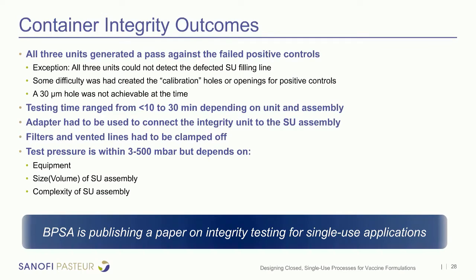So all 3 units generated a pass against the failed positive controls and the negative controls, as mentioned, with the exception of the single-use filling lines. So we were thinking that when we punctured the holes in the filling lines, what was happening was as we passed air through it, it was actually causing the tubing to swell and the hole to close in on itself. So it wasn't detecting the hole. The filling line has a very small inner diameter of 1/32 inch.